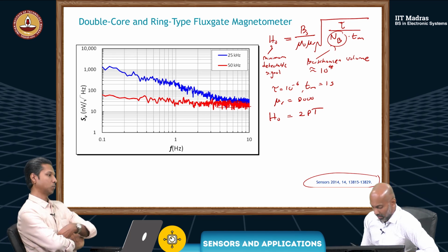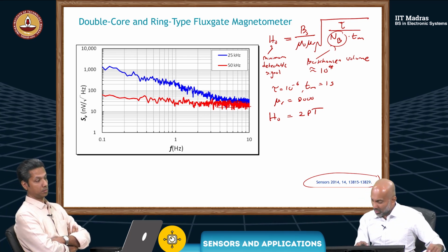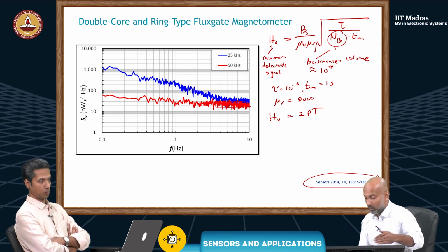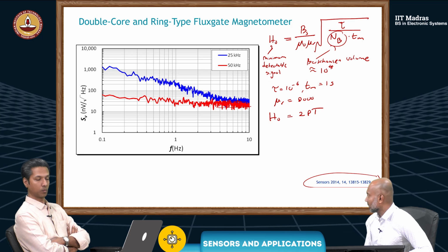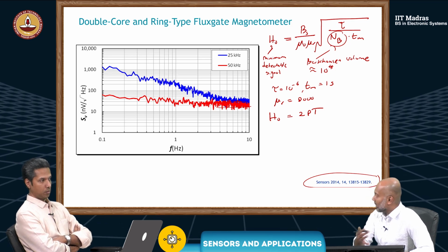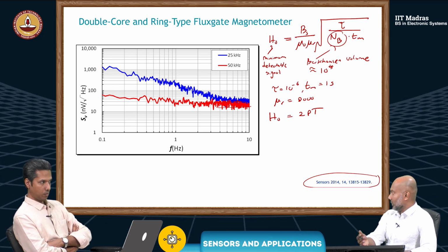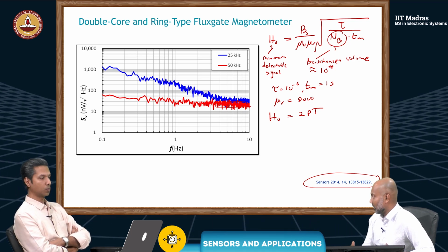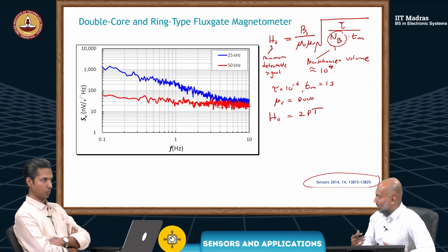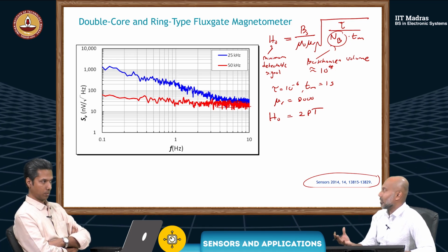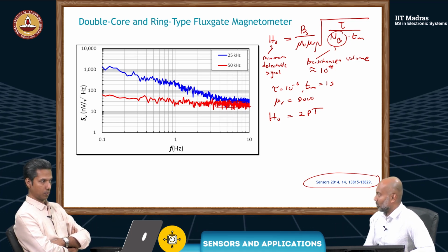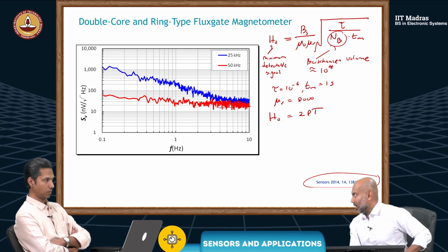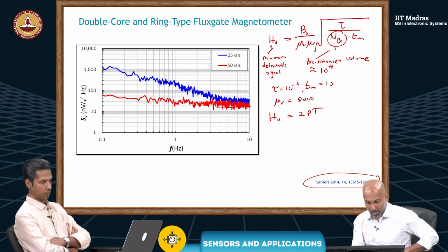Just again, for the search coils, if you look at the search coil, you get a graph like this for the noise. You can use the same techniques that we talked about today to calculate the total noise of your system. The part about the amplifier we already know. So similarly, you can calculate the total noise of the measurement instrument that you're designing.